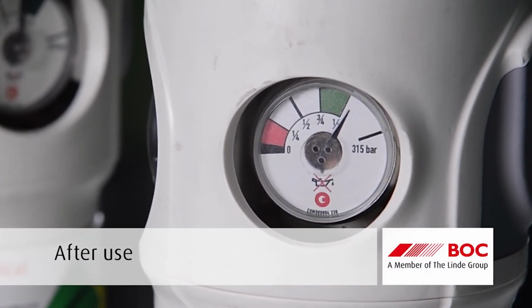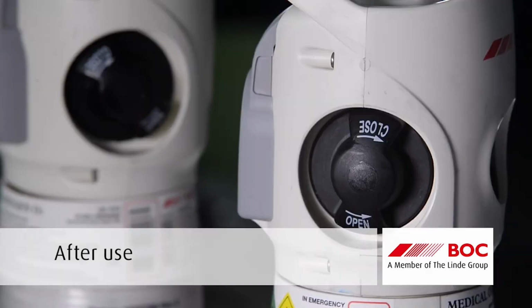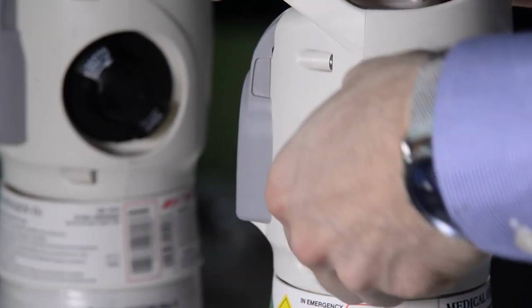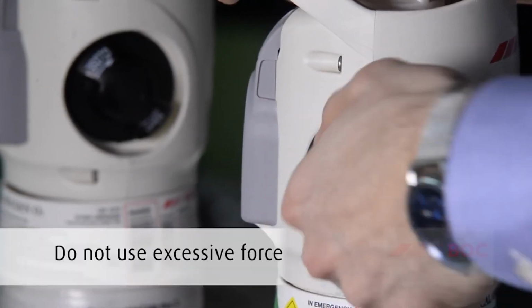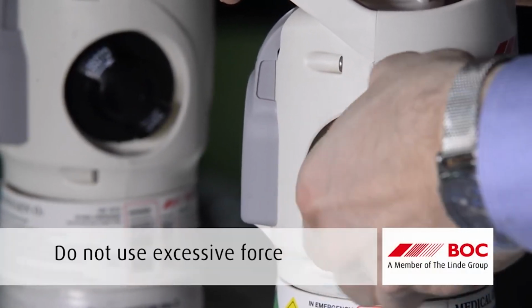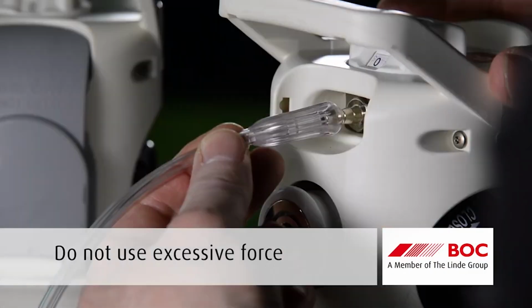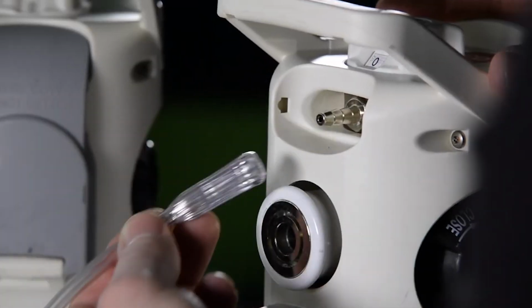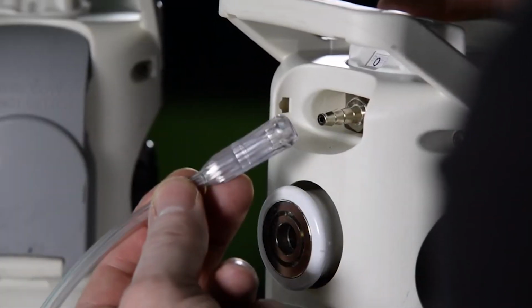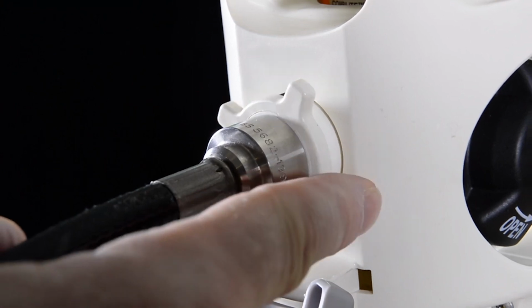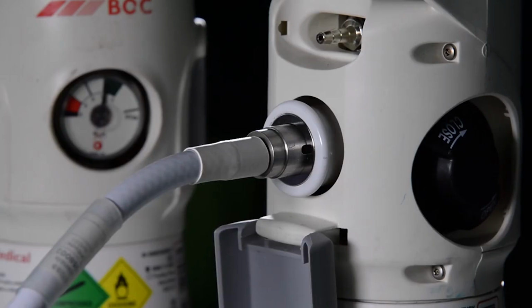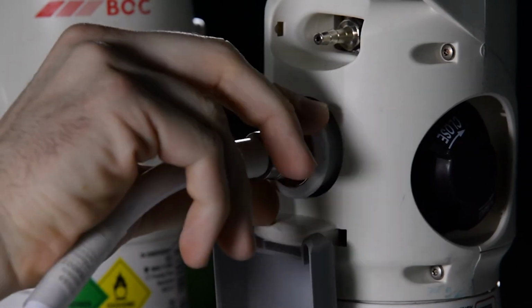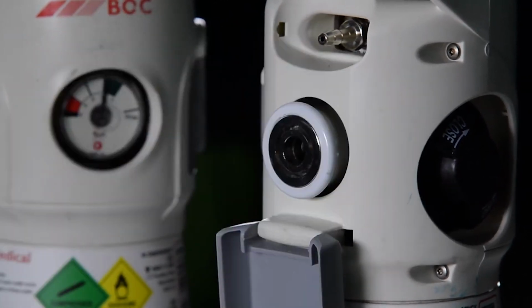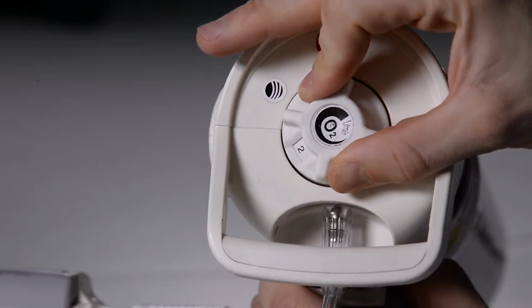Remove the mask or nasal cannula from the patient. Turn off the cylinder by rotating the hand wheel clockwise until it comes to a stop. Remove the tubing by firmly pulling the tube whilst holding the cylinder handle. Release the probe by twisting the capstan clockwise or by pressing the outer circle of a quick connector. Turn the flow selector to 0.